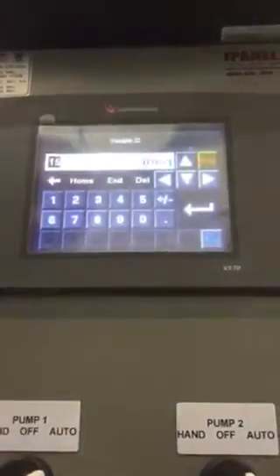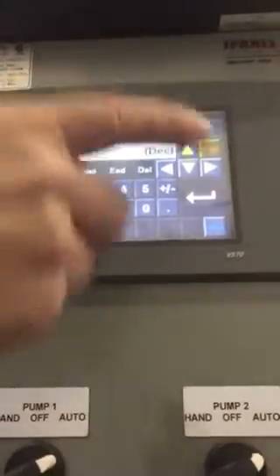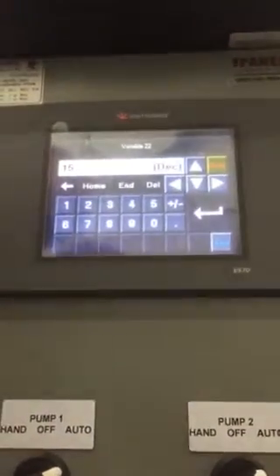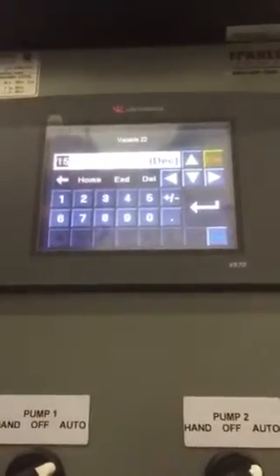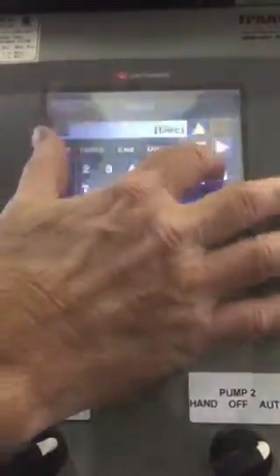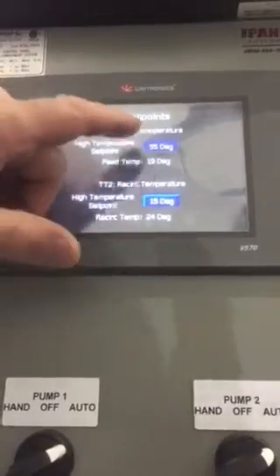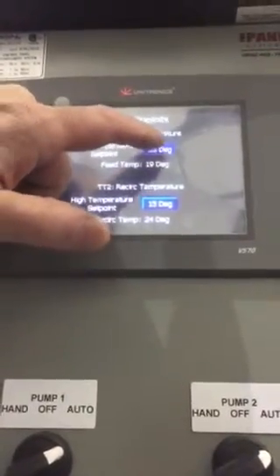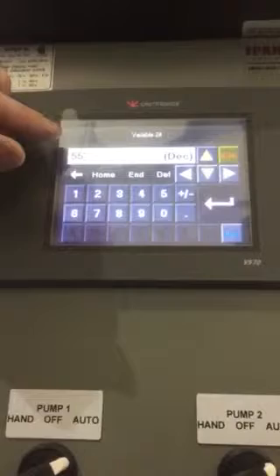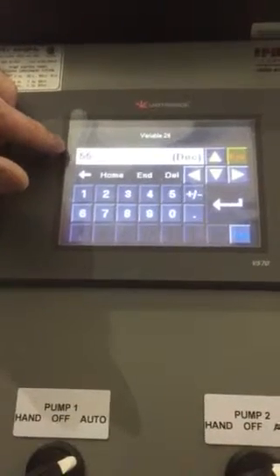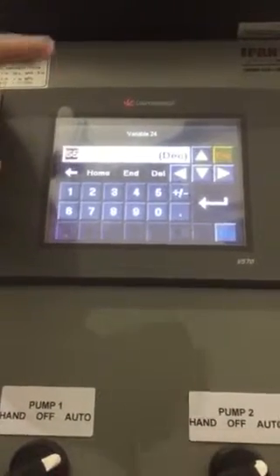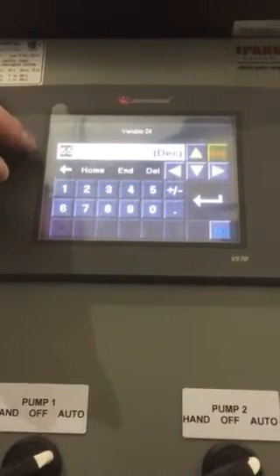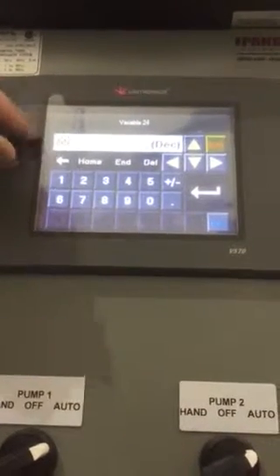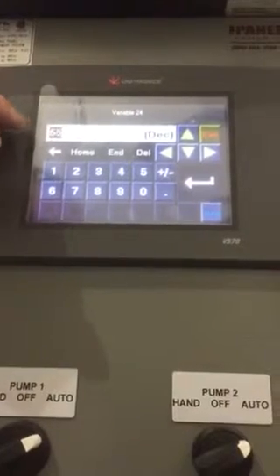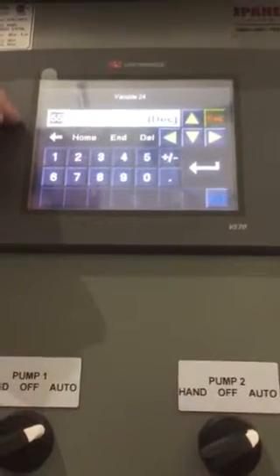This set point can be changed numerically. So you can type in a different number if you want to put in a higher temperature or a lower temperature, and that's where you change that. Same with the set point for the high temperature cutout. This high temperature cutout means that if the feed pump starts pumping liquid any more than 55 degrees right now through the system or into the system, then it'll lock itself out until the temperature goes below that point. I just picked 55 as a number. It can be anything up to probably 80 degrees.